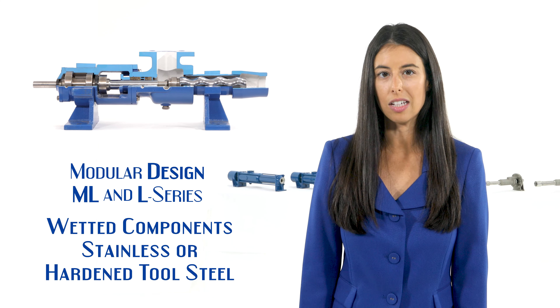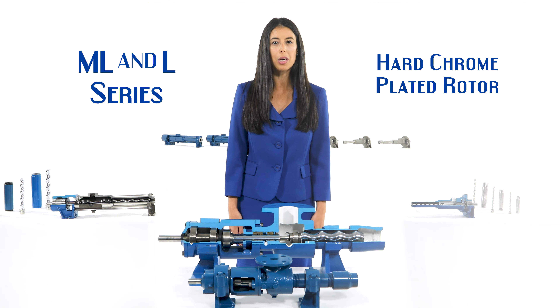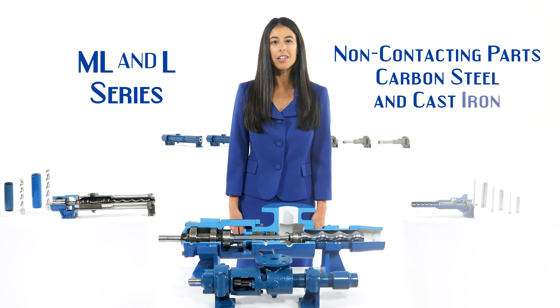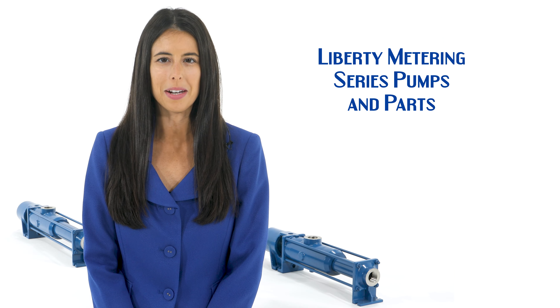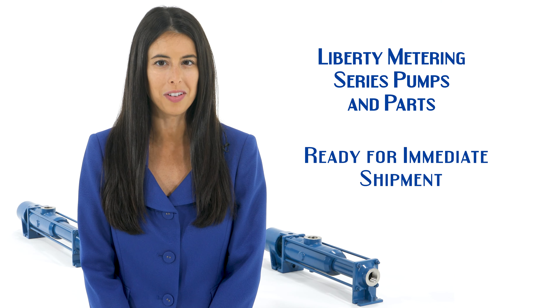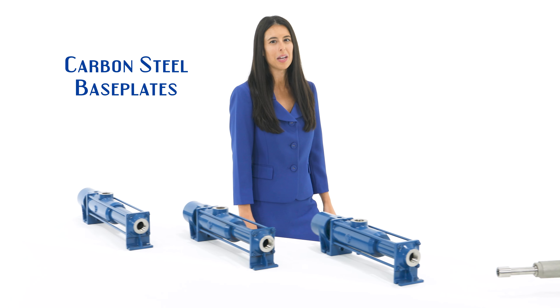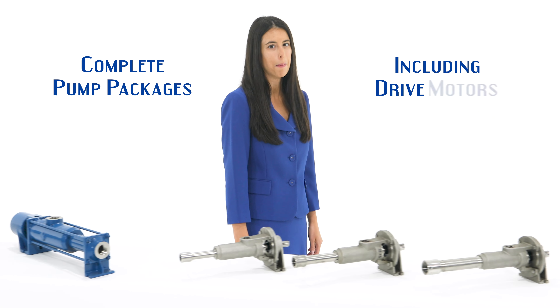The ML and L are based on the very popular Liberty Series of standard flange progressive cavity pumps. They are available with standard ANSI suction flanges and NPT female threaded discharge connections. These pumps range in flows from 0.006 up to 100 GPM and have discharge pressures up to 450 PSI. Stators are available in nitrile, Viton, EPDM, and natural rubber. The standard seal design is a set of packing with a lantern ring and flush connectors.